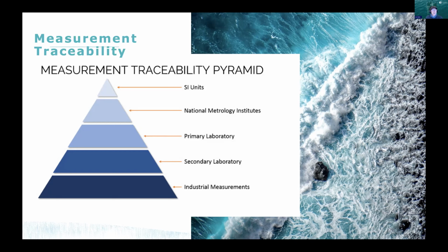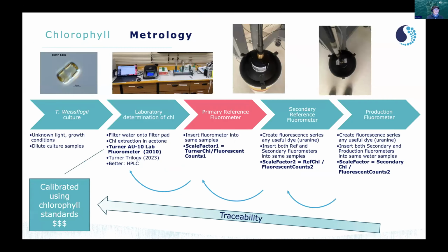But the important thing here is that there's a traceability from the industrial measurements, which in this case are your measurements, to a secondary laboratory, which is us, to a primary laboratory, which might be the instrument supplier that we get our laboratory reference instruments from, and they will tie their instruments to a national metrology institute like the National Institute of Standards and Technology, and ultimately into what we call SI units, which is meters, kilograms, seconds, and so on. And there are international and national institutes that keep track of those things.